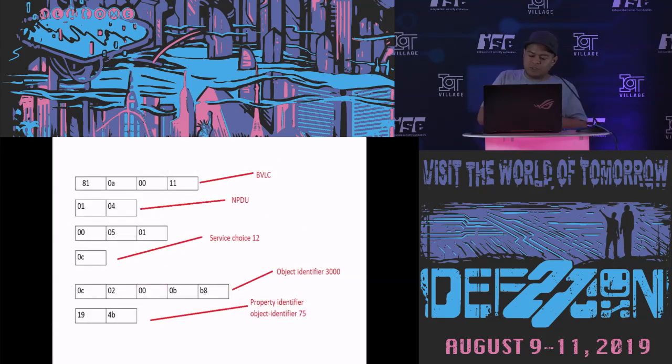So if you want to read a property identifier and an object identifier inside that device, you need to send a packet that looks like this. You will see the service choice, which is 12, properly configured, and then the object identifier.